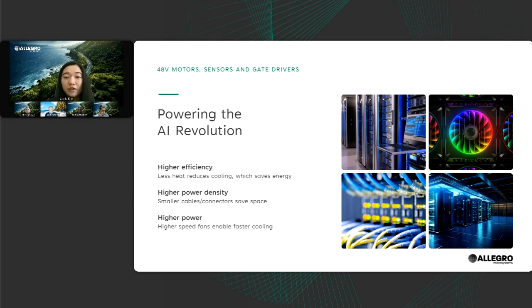Converting from high voltage power to lower voltages results in energy losses, but a 48 volt system reduces that step-down conversion loss compared to 12 volt systems, leading to improved overall energy efficiency. This is particularly important in AI data centers where power consumption is already very high. Because 48 volt power distribution can handle higher power densities more efficiently, there is less heat generated by power losses, which reduces cooling requirements and overall saves energy.